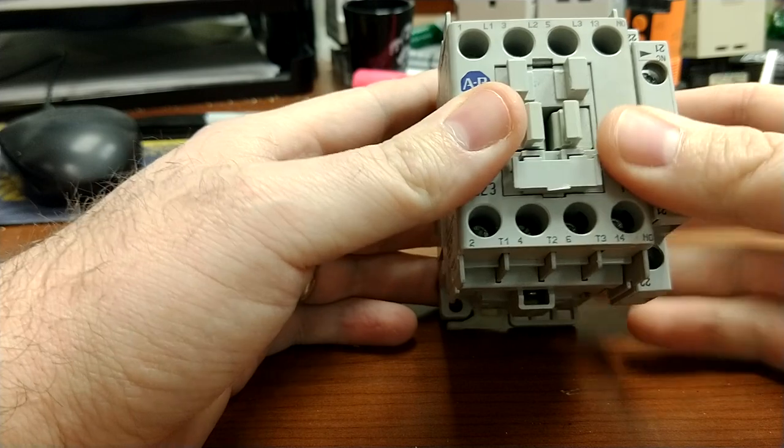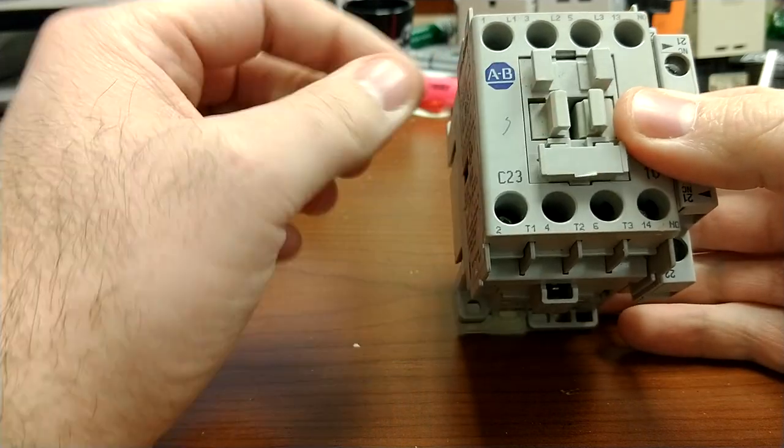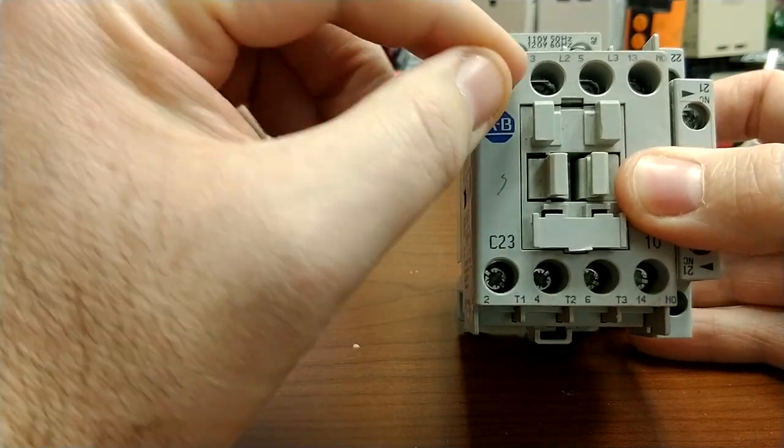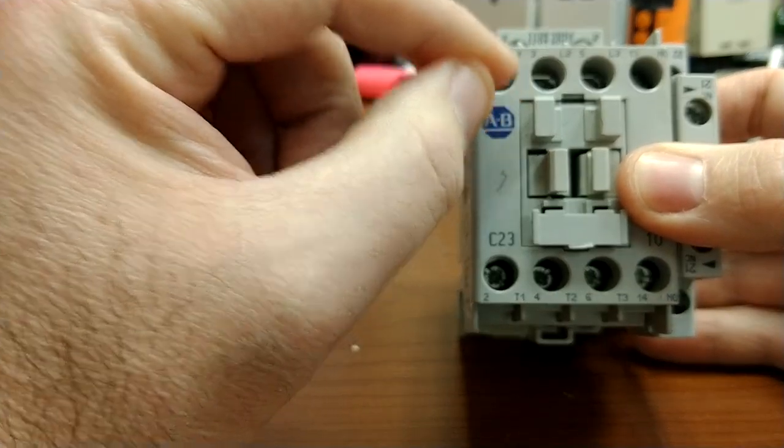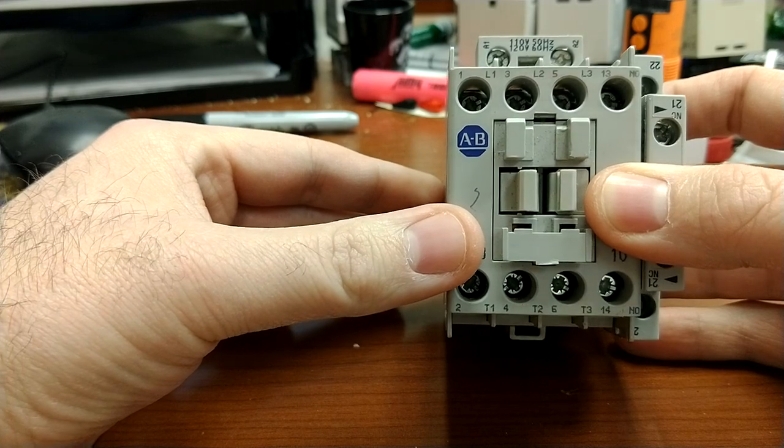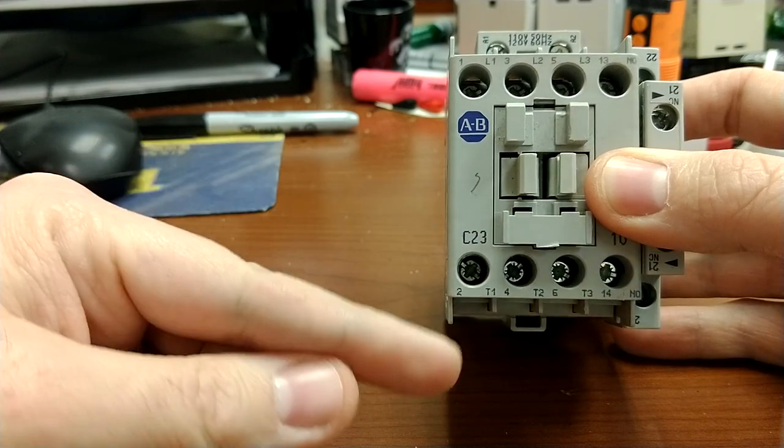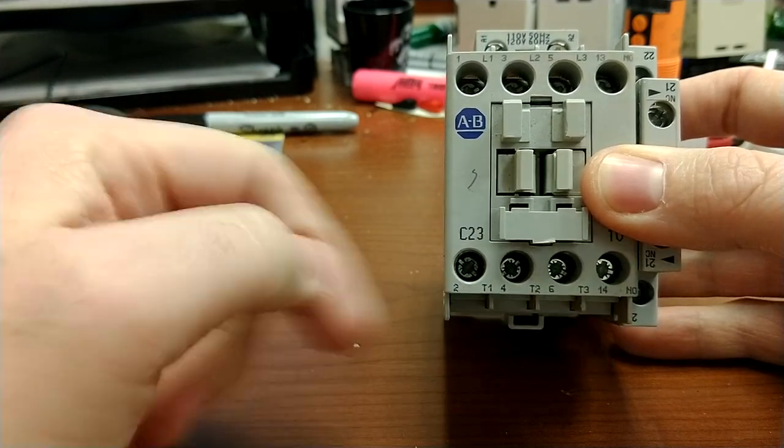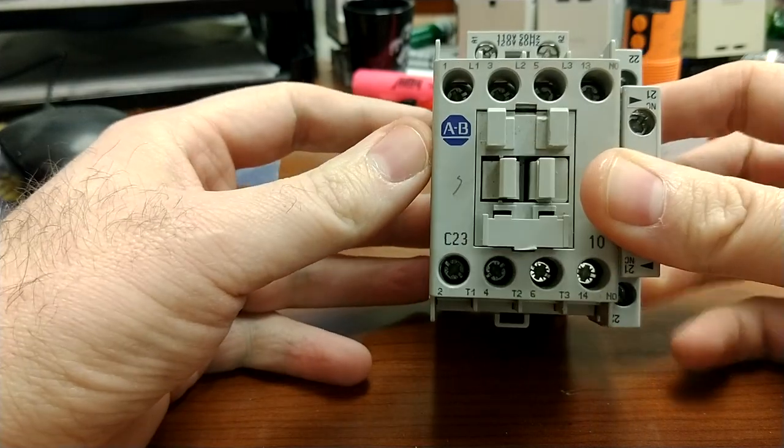A1, A2, which is just like your coil, but in theory, it works the same way as a relay. Power comes in to the coil and out, and it induces a magnetic field that pushes in this relay contact right here that basically then takes it and shuts it. And it does that for all three poles of the contact. Now, a couple things you can see when we use contactors, you're usually using L1, L2, L3 with a T1, T2, T3.